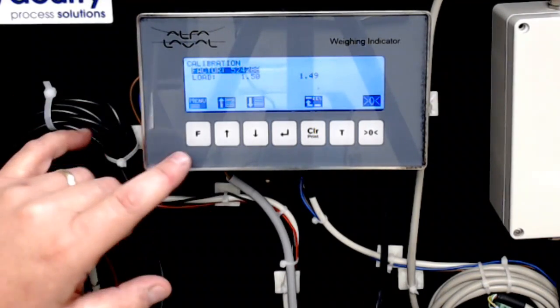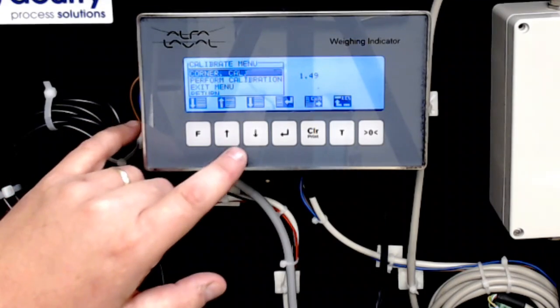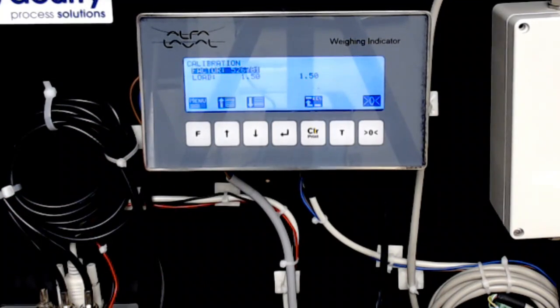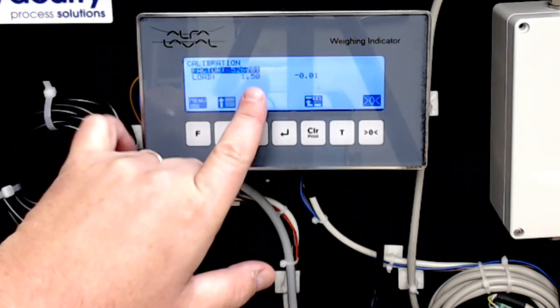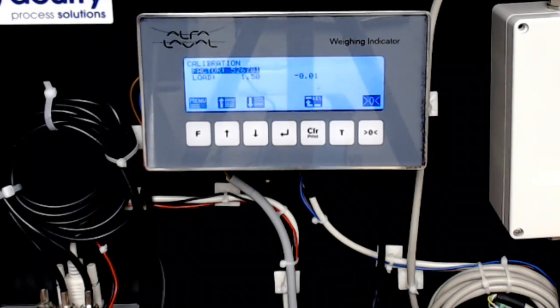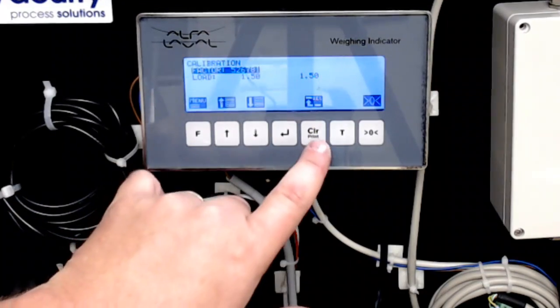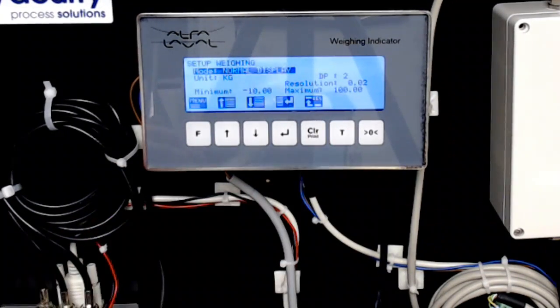Once I enter that in there, I hit menu again and I say perform calibration. And once I do that, now you look at the two numbers, they're the same. The system is calibrated. If I take this off, you'll see that it drops down to nothing. But if I put it back on again, and actually this is not a good sample because I don't know for sure, but there's the 1.50 again. So that's as simple as it is to perform a calibration on this system.